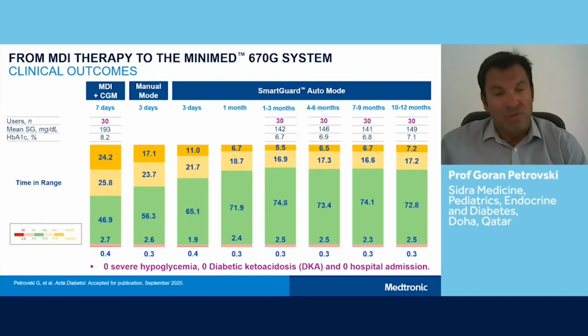The first point is the automation, so the algorithm of the MiniMed 670G adjusts the basal insulin delivery, and the second point is that we were more aggressive in changing the carb ratio. So when we evaluated the 3 days of manual mode, if we saw that the postprandials were high, in most of the patients, if needed, we changed the carb ratio immediately with the initiation of the auto mode. After the first month in auto mode, the time in target range increased above 70%, almost 72%. In the 3 months, it reached almost 75%, and in the following 6, 9, and 12 months, it was maintained above 70% during the study and ended up at almost 73%.